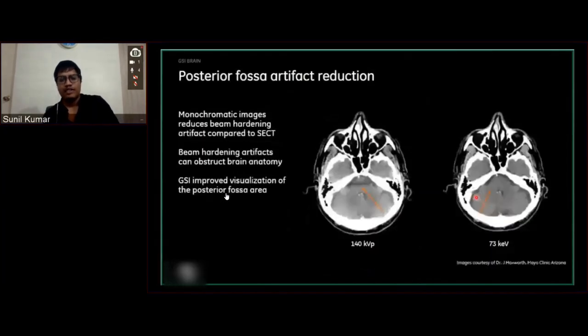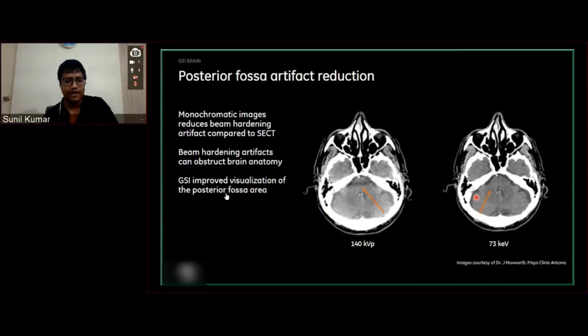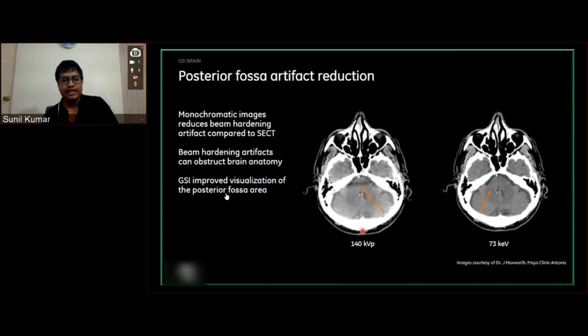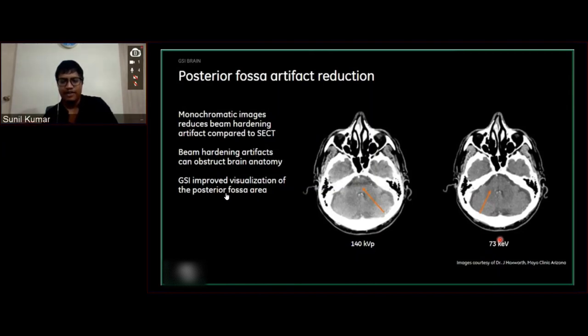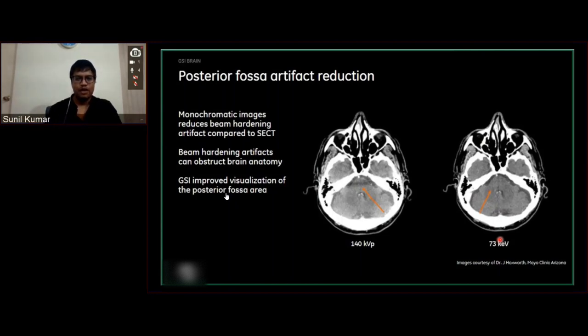Another benefit of monochromatic images is detecting posterior fossa beam hardening artifacts. This is a normal challenge for everybody in the industry — all technicians may have experienced this posterior fossa artifact in conventional CT. This can be reduced without exposing the patient again, just by changing to a mono keV technique. Just use the slider to change energy levels ranging from 40 to 140 keV — you will definitely see a change that will eradicate the beam hardening artifacts in this particular case.